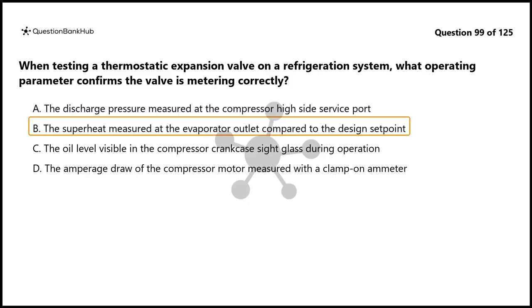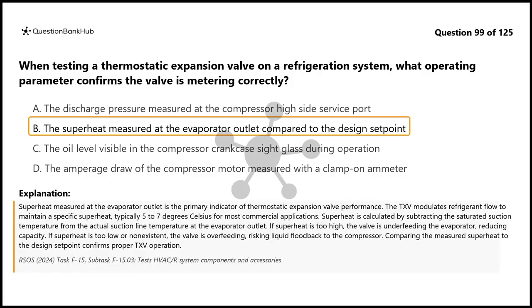The correct answer is B. Superheat measured at the evaporator outlet is the primary indicator of thermostatic expansion valve performance. The TXV modulates refrigerant flow to maintain a specific superheat, typically 5 to 7 degrees Celsius for most commercial applications. Superheat is calculated by subtracting the saturated suction temperature from the actual suction line temperature at the evaporator outlet.